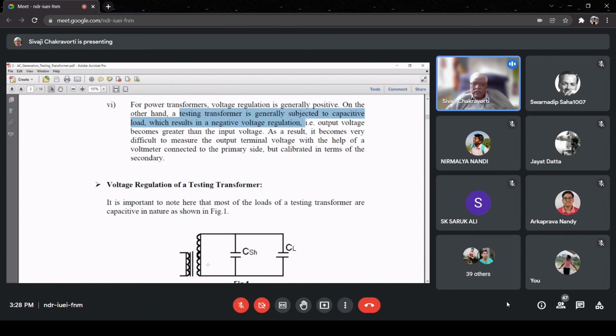Or effectively, what will happen is, if I am supposed to test at 100 kV, I have calibrated my voltmeter at the open circuit condition. Then under load condition, that means when the equipment is connected, the voltage will be higher than 100 kV. That means I am testing at a voltage, say 105 kV. And the equipment fails because it is not designed for 105 kV. Now, this is not a fault of the equipment designer. This is a fault from our testing side. I have not taken proper care.